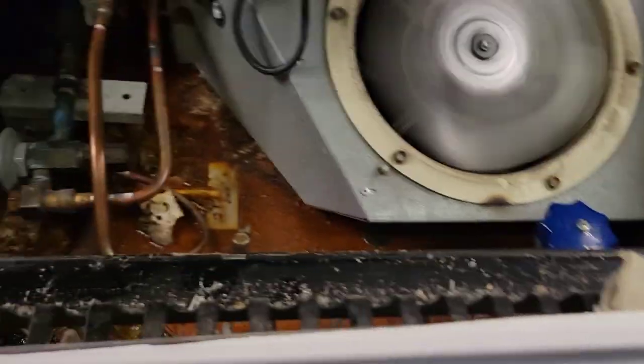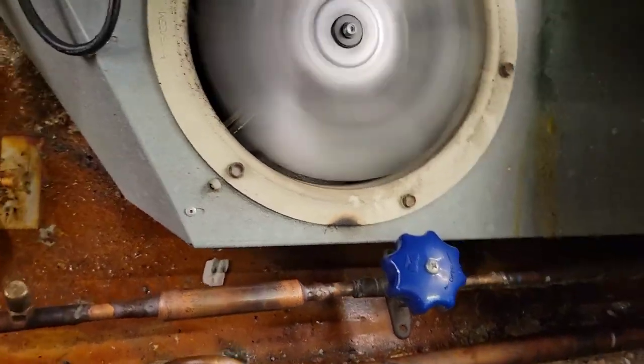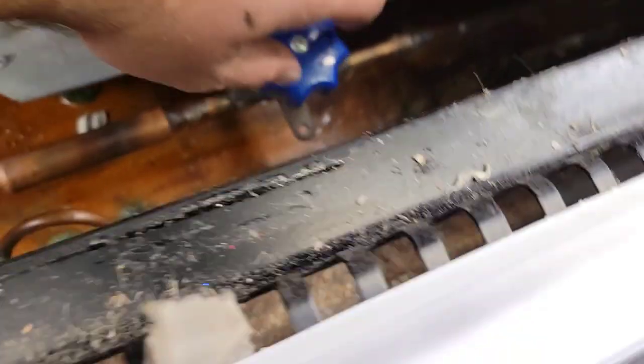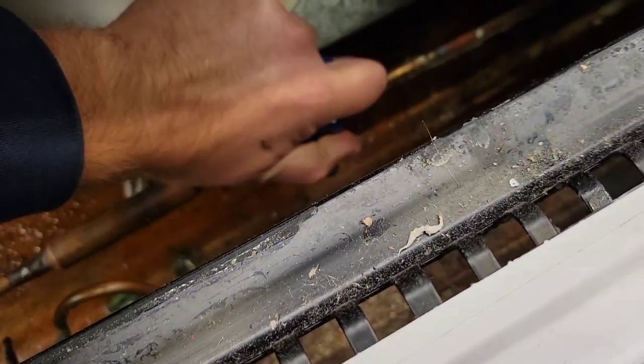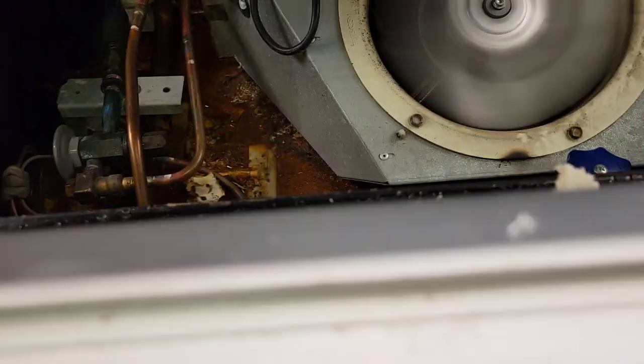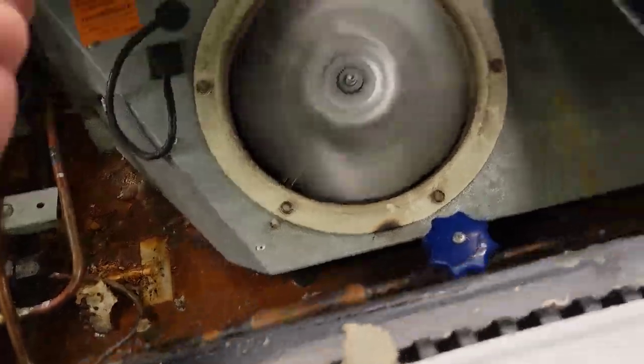All right, there's no filter dryer down there, but I'm still gonna check the other side just in case. And we have a hand valve. While I'm here, I almost always check the hand valve because, believe it or not, technicians leaving hand valves off, or stores hiring cleaning companies to clean their cases, is super common. So I'm gonna move on and check that other fan, and then we're gonna move up to the rack.